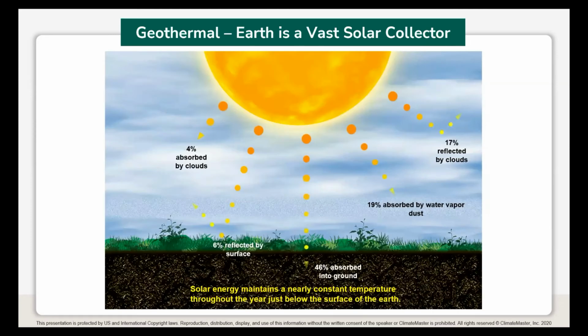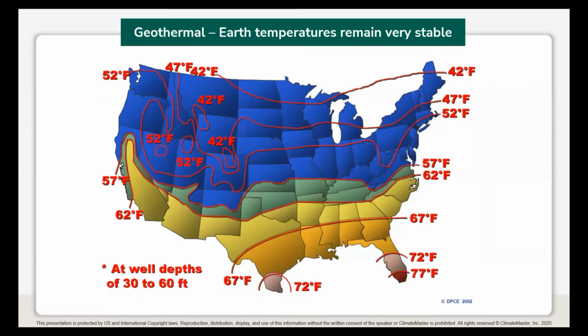heat pump. It's a renewable energy, and it is classified as such because it uses the sun warming the earth as the basis of its operation. So most of the heat that is generated by the sun is absorbed into the ground, and there are clouds and reflection and surface reflection, but most of it is absorbed into the ground. Below 5 feet or so, the earth stays a constant temperature. So you'll see by this chart that you will hover somewhere between, I don't know, probably 45 and 52 degrees as your constant stable ground temperature.